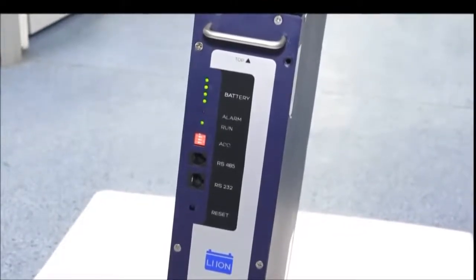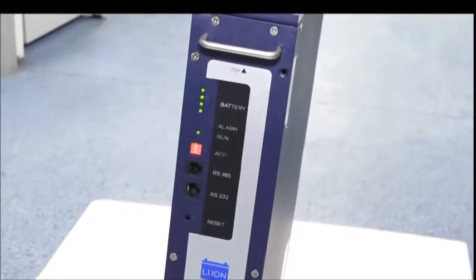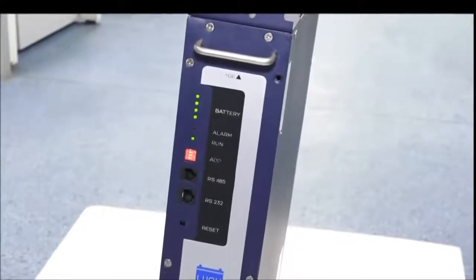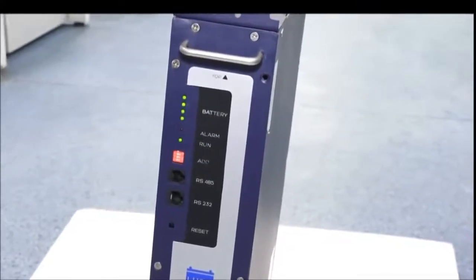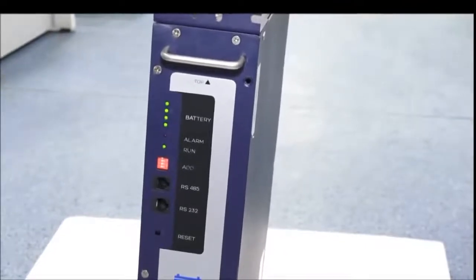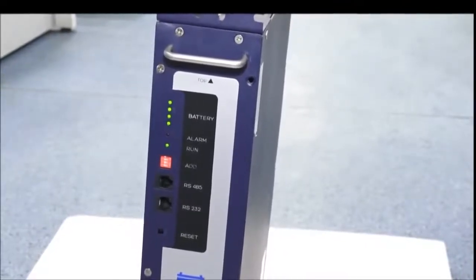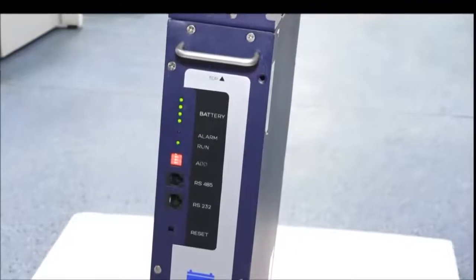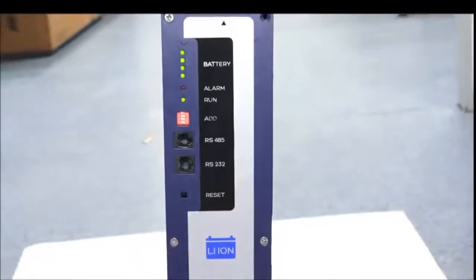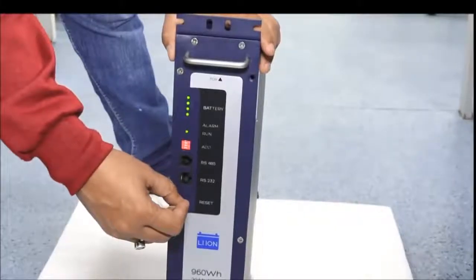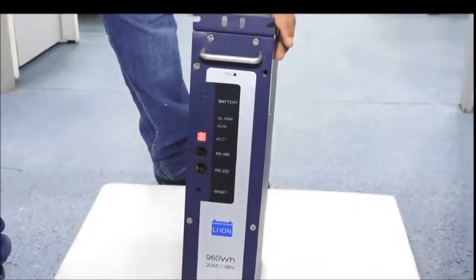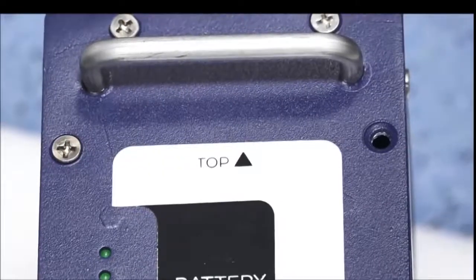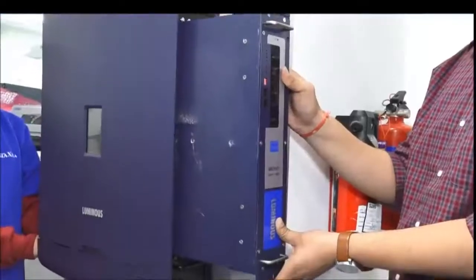If the battery and run LEDs light up together, the battery is okay. If they do not light up together or the alarm LED lights up, contact the CSQ team and get the battery replaced. To turn off the battery, press the reset switch again. This is the top side of the battery. Make sure that it is pointing upwards.